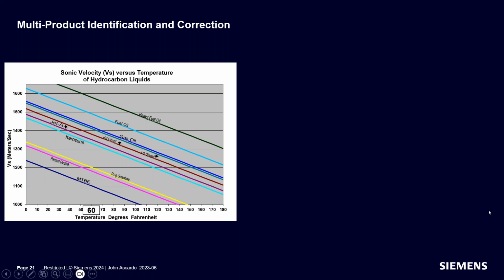But look at this chart. Suppose that my meter was measuring a speed of sound of 1400 meters per second. If I was to say to you, well, what fluid am I flowing? I just shrug my shoulders and say, I don't know. There's a whole bunch of them. It could be any of them. It could be kerosene, it could be fuel oil, it could be gas, it could be diesel. There's no way to know. The only way to know is to say, well, what is the speed of sound and what is the temperature? And then normalize that temperature to 60 degrees. So if we do that, then there's no question as to what fluid it is.